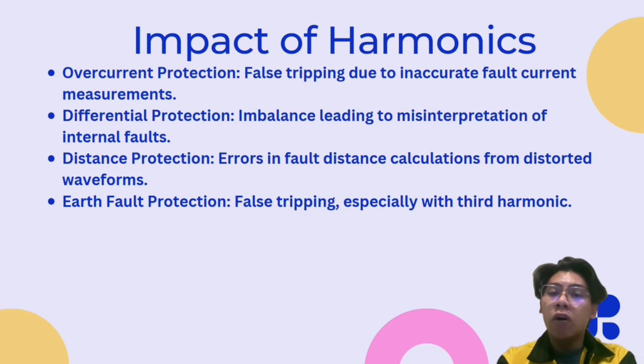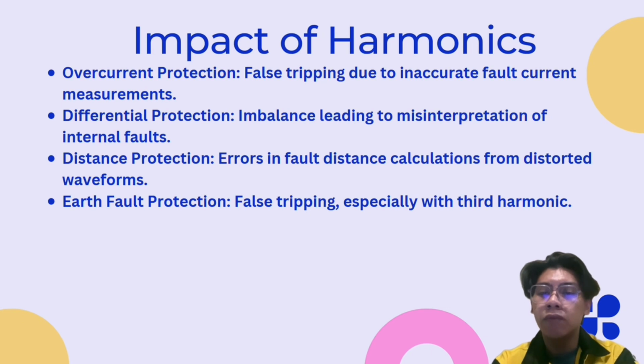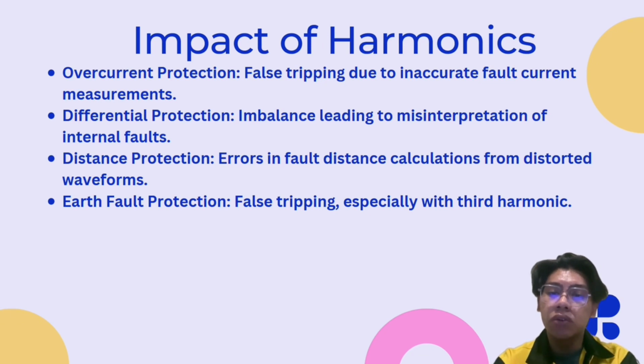And then next one is the impact of the harmonics. The first one is the overcurrent protection, which has false tripping due to inaccurate fault current measurements. The second one is differential protection. Imbalance will lead to misinterpretation of internal faults. The third one is distance protection, which will cause errors in fault distance calculation from distorted waveforms. And the last one is earth fault protection, which will cause false tripping, especially with the third harmonic.